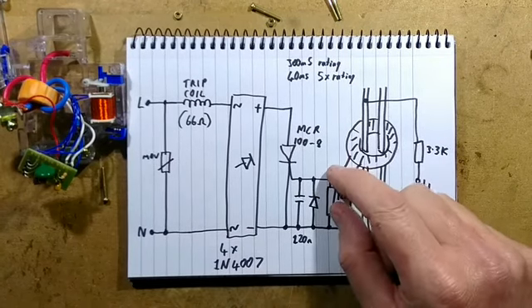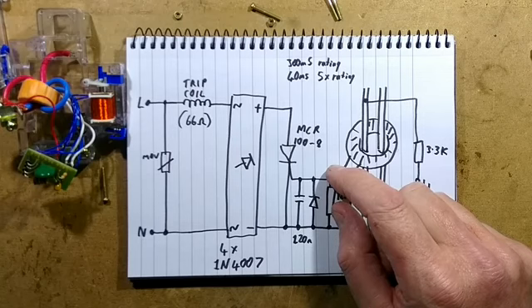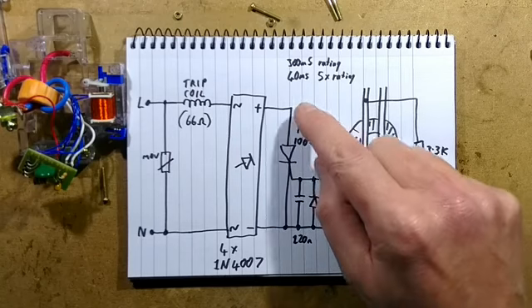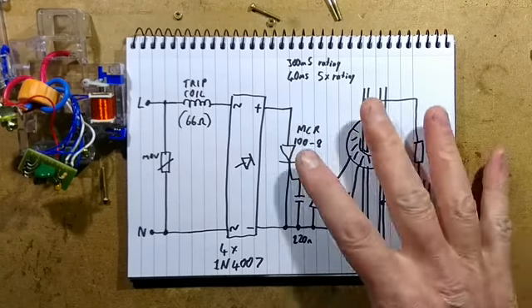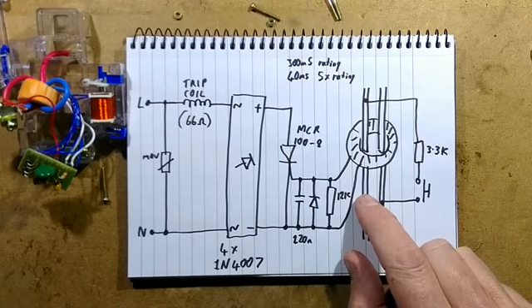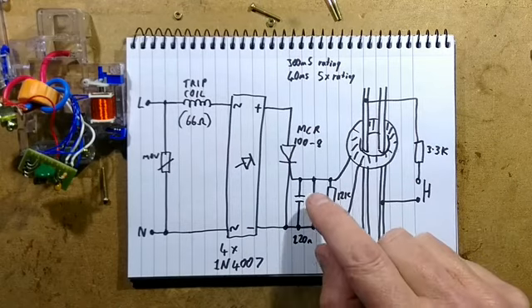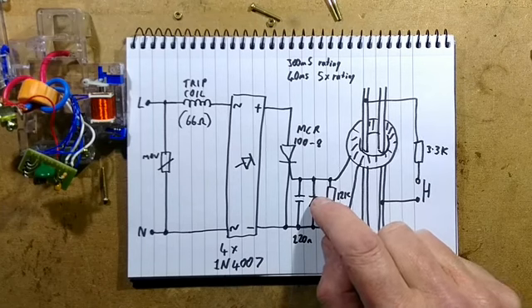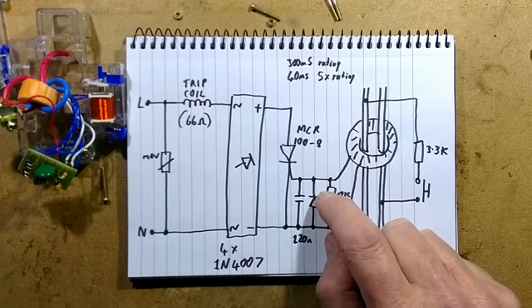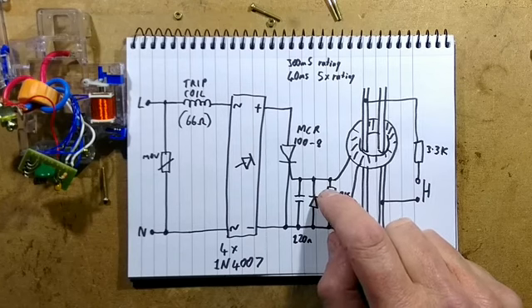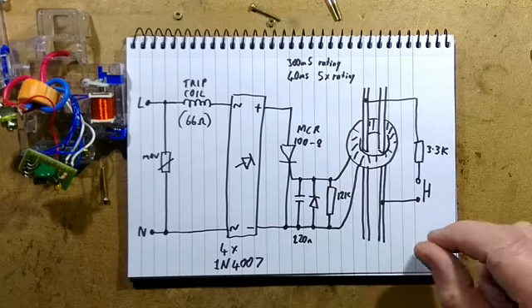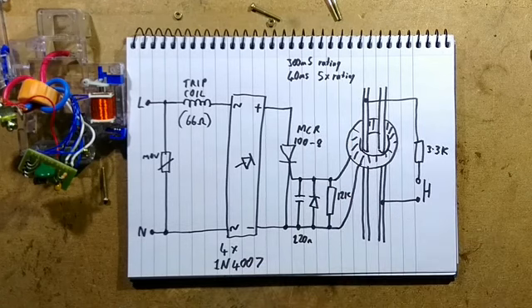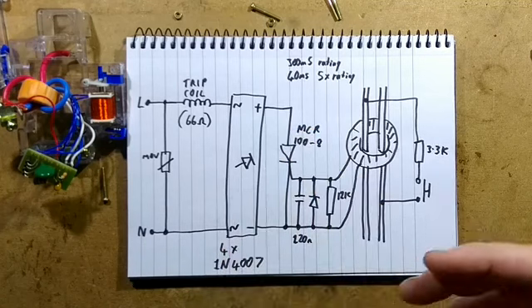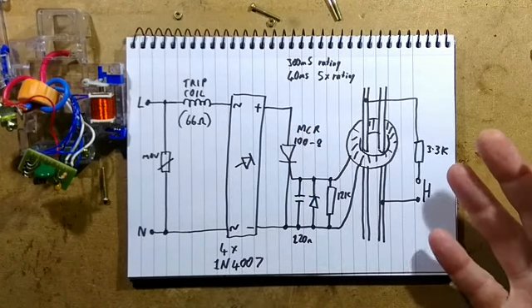The trip times I was getting were well within the standard British requirement, actually. The requirement in Britain is that at normal current, say this is a 30 milliamp RCD, it should trip within 300 milliseconds. That seems quite a long time, because let me assure you that if you get yourself into the situation that current is flowing through your body, 300 milliseconds, even though it's just 1/3 of a second, will feel like a very, very long time. At 5 times that current, it should trip in 40 milliseconds, and that's a sort of minimum time it should trip in.